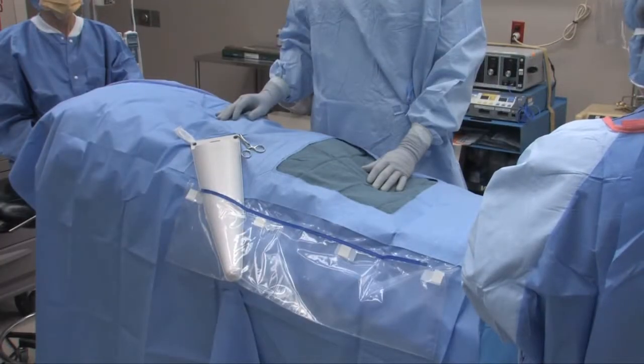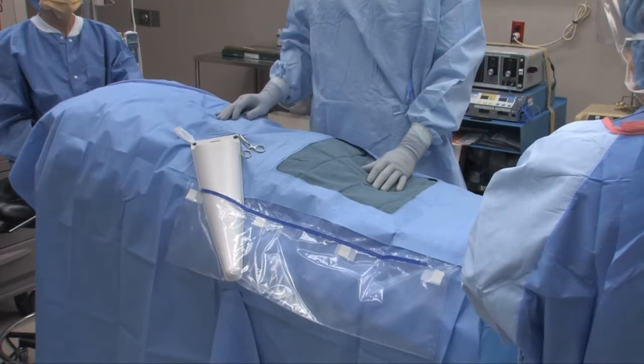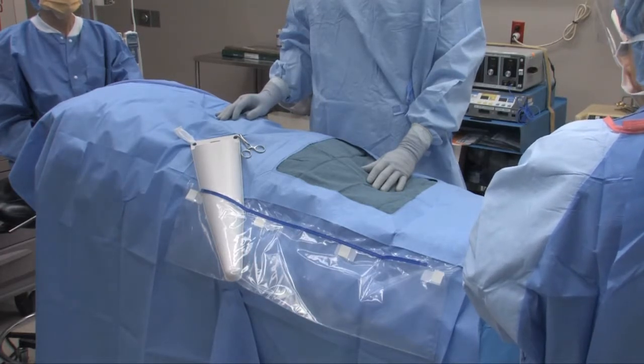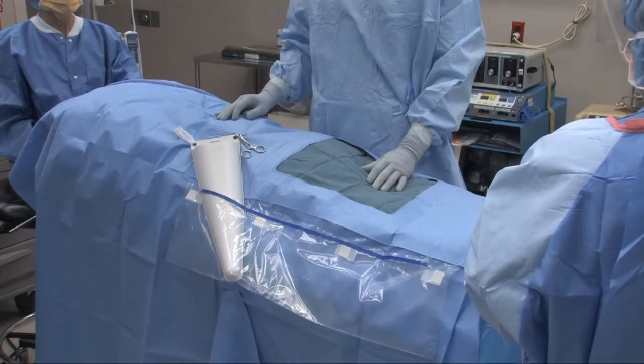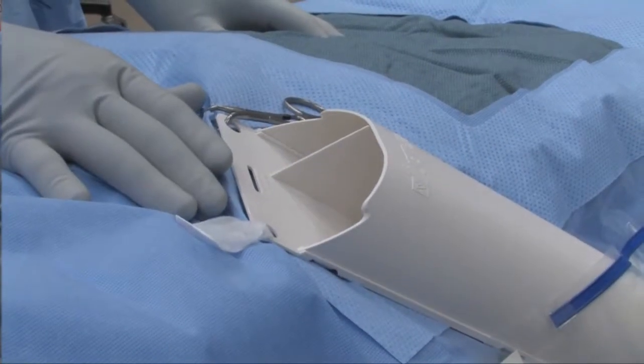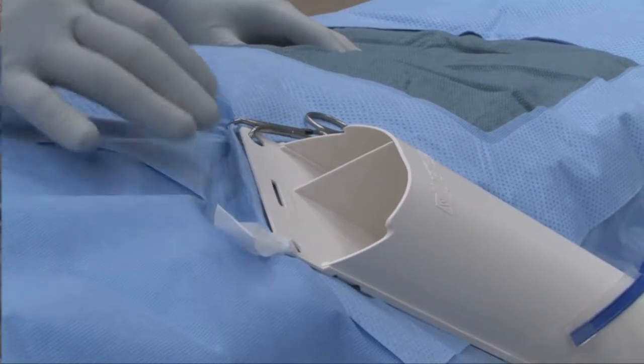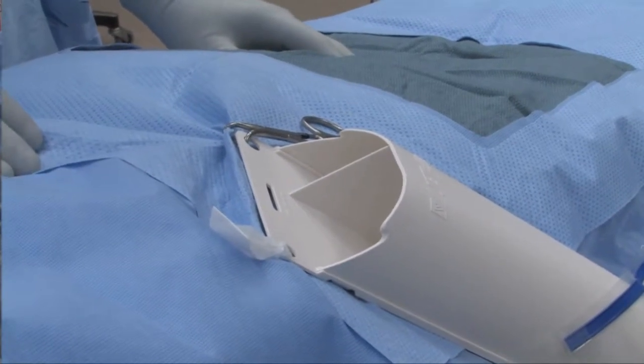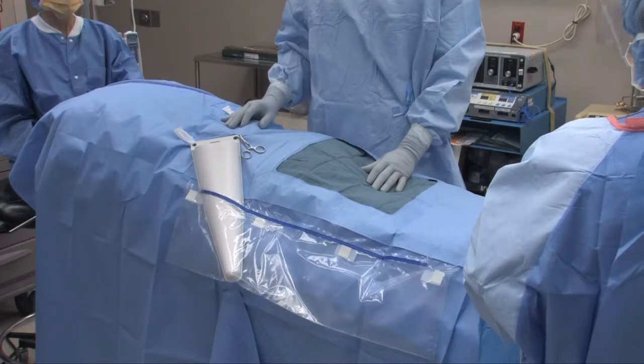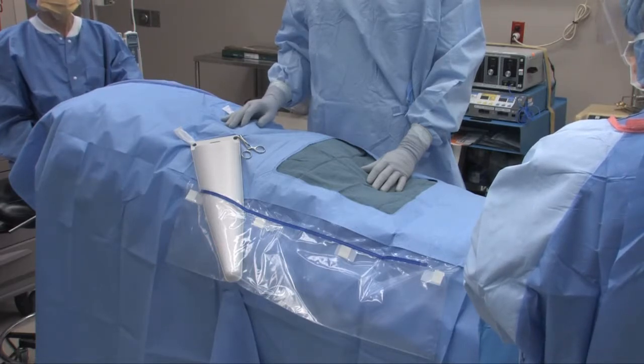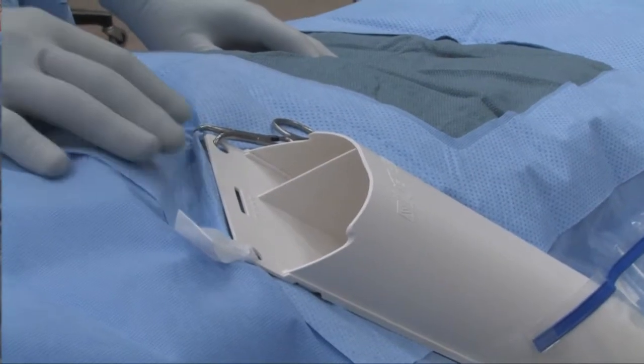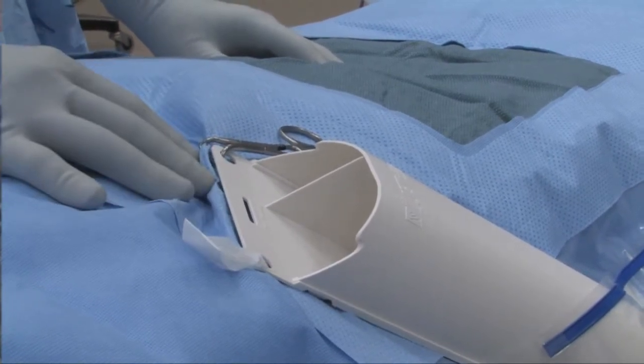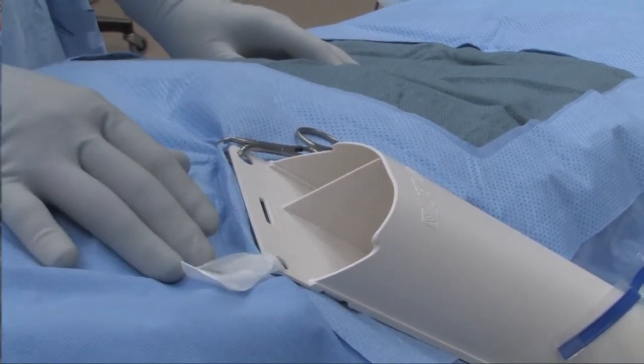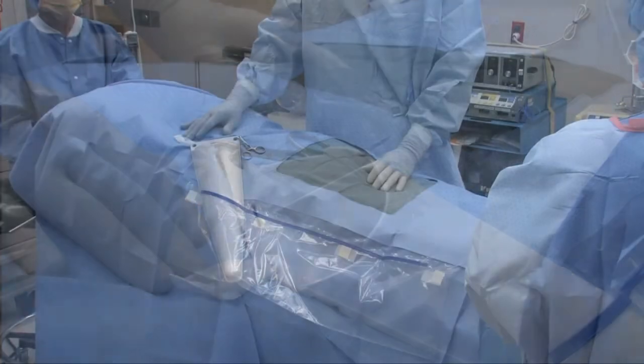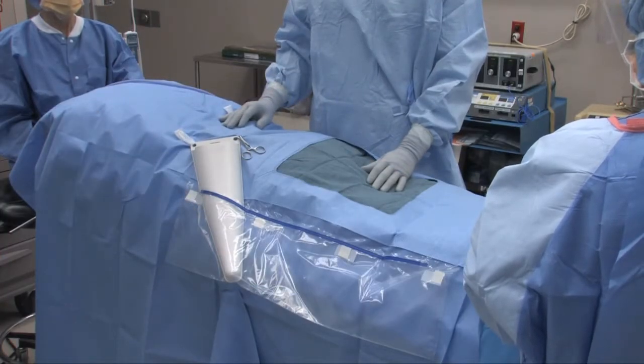The holster can be placed on the sterile field according to the operator's preference. The device should be attached to the sterile field in a vertical fashion using fastening holes located on the top flange of the device. It may be helpful to locate it across from the operator for ease of access and organization. It is recommended that the device be secured by at least 2 of the fastening holes. Examples include non-penetrating towel clamps or the self-adherent straps commonly found on surgical drapes. The device should be maintained above the sterile field at all times.